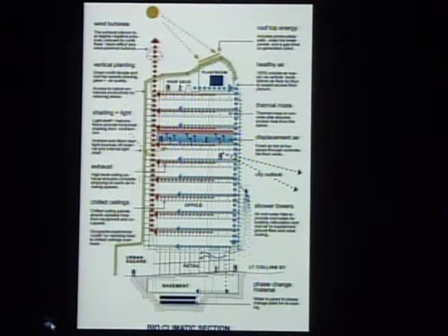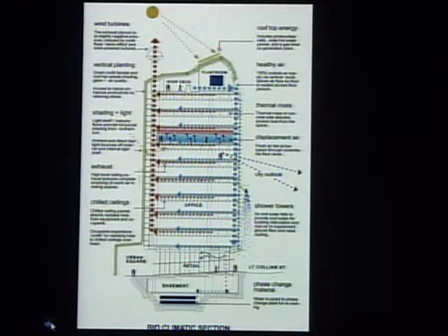What we're doing is taking the heat out of the offices, the 9 floors of offices, and dumping it in the basement thermal store, recirculating cold air. We're moving the heat from the offices down into the basement, where we have a thermal store, which I'll show you next. The exhaust air goes up the chimney, and the supply air comes down from above, cooled to 20 degrees, or warmed in winter up to 20 degrees by machines on the roof. The air going out would be at about 25, 26.